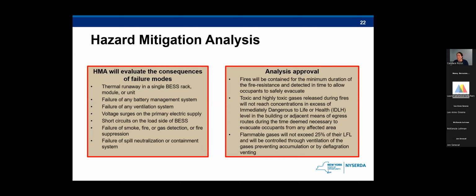So here we have the requirement for the hazard mitigation analysis. This is only required for energy storage technologies that were not listed in that initial scope, when there's more than one technology provided in a room or enclosed area, or where allowed as a basis for increasing the maximum allowable quantities. We'll get to the maximum allowable quantities in a few slides, but really what that is stating is that any lithium ion system over 600 kilowatt hours will be required to perform this analysis.